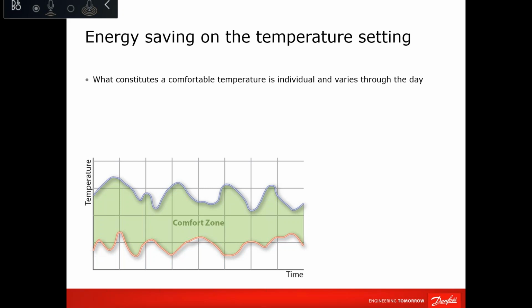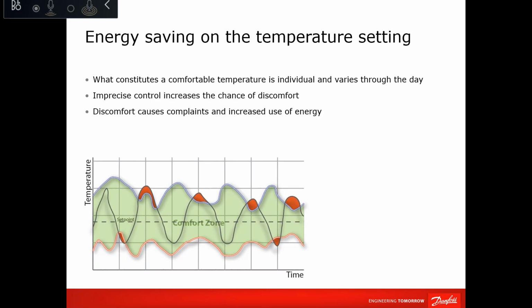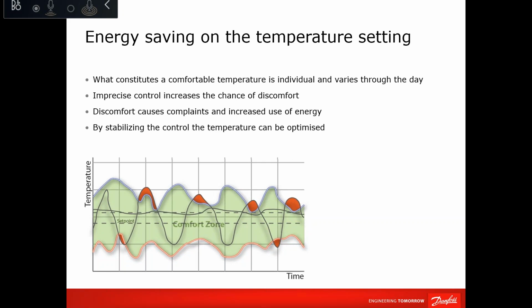The last part of the saving is the comfort level. So now in a normal two-way valve, we have an unbalanced system, which means that the flow will be oscillating up and down due to the pressure dependency of the two-way valve. And if you have an unbalanced hydronic system, you will have unbalanced thermal distribution, which means some of the rooms will be feeling hot, other rooms will be freezing, regardless of the set point on their respective thermostat.